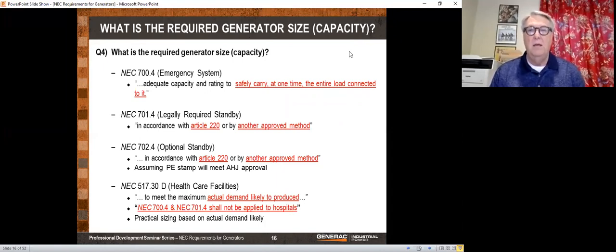They say it used to be with Article 220, that's the article when you build your house and you go through there and say, I got this many square feet, I'm going to have this many receptacles and all that, and it tells you how big your service needs to be. That's a terrible way to size a generator, because you're going to get a way oversized generator. You can imagine if you have a service on the outside of your house that's 200 amps, but you may never pull more than 30 or 40 amps in your house. Well, going with Article 220 is a terrible way to do it.